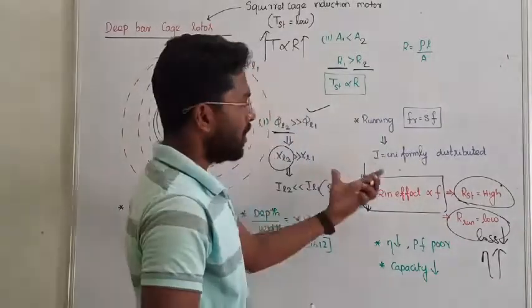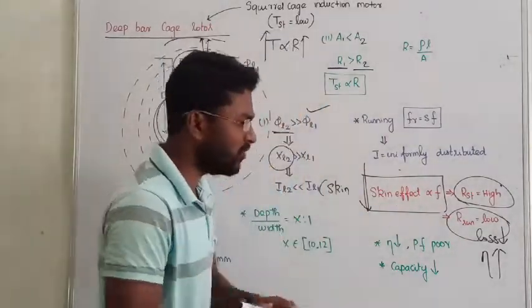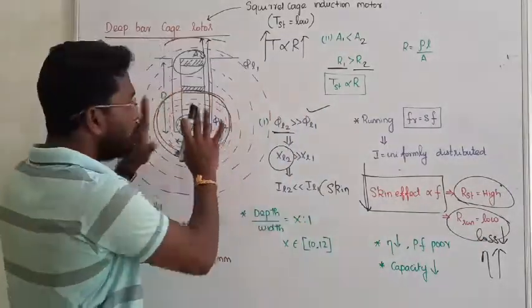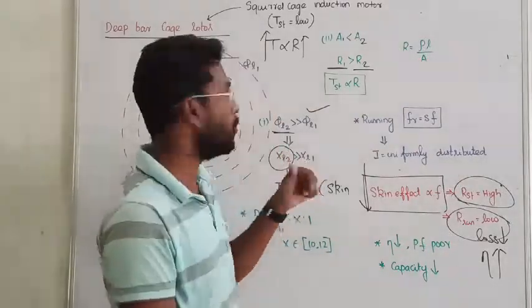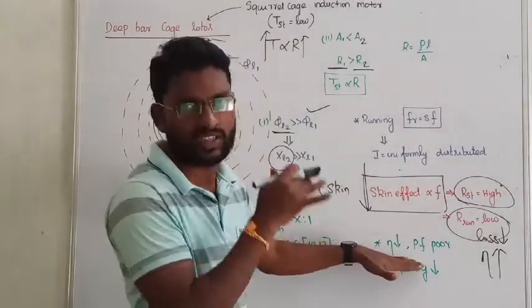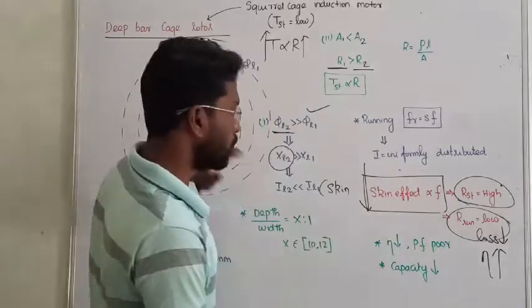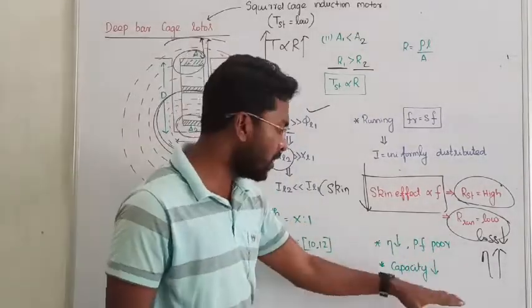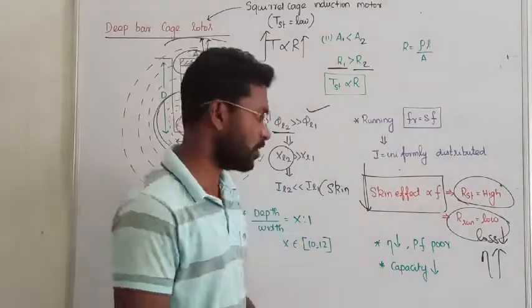But if we compare deep bar construction with normal machine without deep bar, efficiency is less, power factor is poor. Capacity of the machine due to this deep bar is reduced. These are the few drawbacks of the deep bar cage.